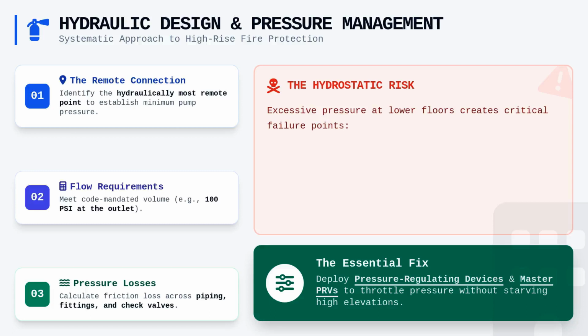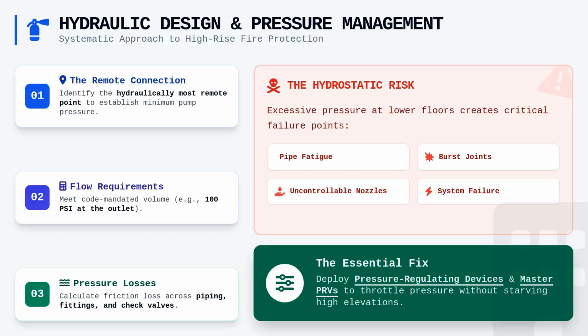This is where pressure regulating devices and master pressure reducing valves become essential, as they allow us to throttle excessive pressure down to manageable levels without starving the higher elevation connections. You cannot simply build a tall riser and pump the hell out of it, because the resulting hydrostatic pressure at the bottom would likely lead to pipe fatigue, burst joints, or an inability for a firefighter to hold the nozzle.